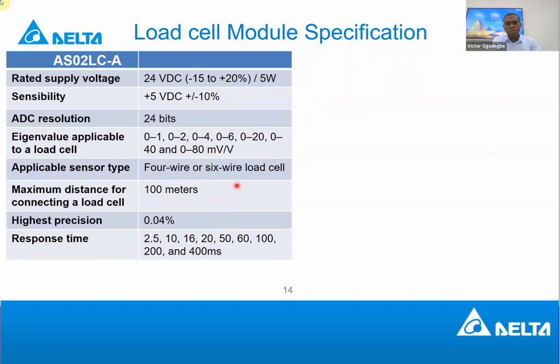Let's bridge this to selecting a load sensor. Looking at this, if you want to select a load sensor, how is this applicable to that? The excitation voltage. For our load cell module, AS02LC-A, the excitation voltage is 5 volts. So if you want to use a load cell, a load sensor on this module, you need to choose a load cell that supports 5 volt DC and above. If you have a sensor that requires more than this, it means that you cannot use this module. If you have a sensor that requires lower than this, you also cannot use it, because this excitation voltage is supplied to the load cell.